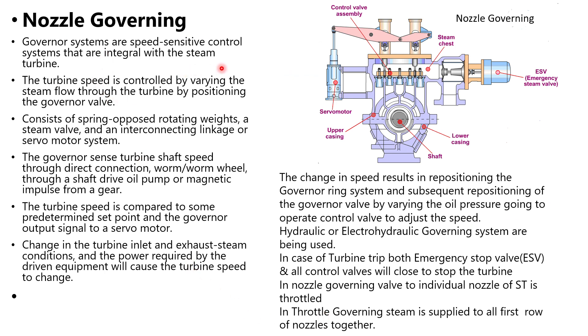In nozzle governing, the turbine speed is controlled by varying the steam flow through the turbine by positioning the nozzle valves. These valves are loaded by a spring; a spring closes the valve and when steam pressure goes up it opens the valve. The governor senses turbine speed and adjusts accordingly. The turbine speed is compared to the set point and the servo valve is operated accordingly. The valve is then repositioned. Governing can be hydraulic or electro hydraulic, and in case the turbine trips, both the emergency stop valve and all control valves will close immediately.